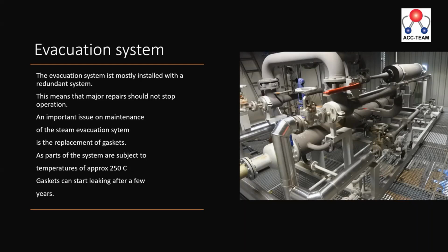I said, well, you used a few faulty pumps, and that is costing you a lot of money because your operation goes down. But later on, we did some maintenance on the steam ejector system, and that was the solution to the problem.